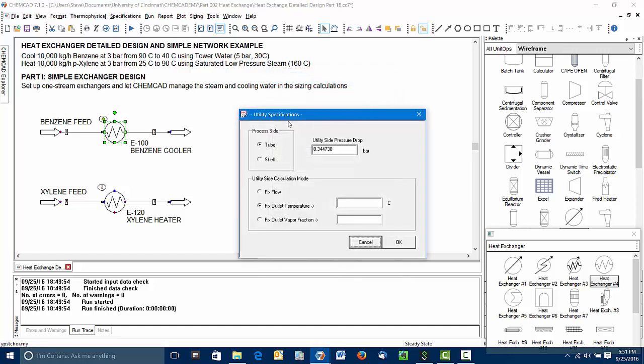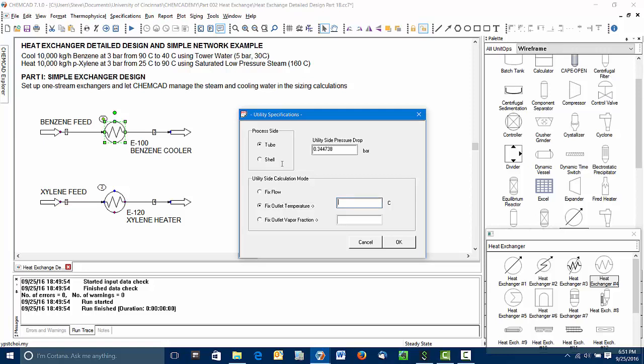We need to tell ChemCAD explicitly which side is the process side, which side is the utility side. As we just discussed, the benzene should be on the tube side. ChemCAD has provided here a rule of thumb pressure drop for the utility side. Now we need to fix a specification for the exiting utility. For cooling water, our typical rule of thumb is that it shouldn't leave any hotter than 50 Celsius, 120 degrees Fahrenheit.